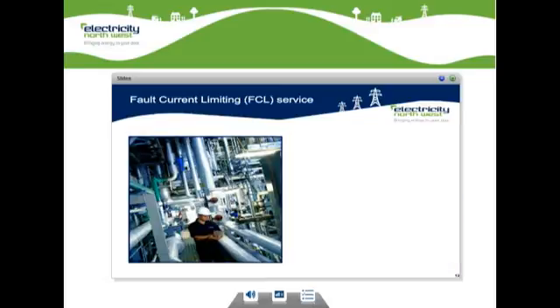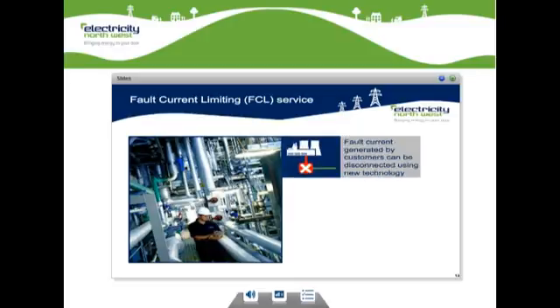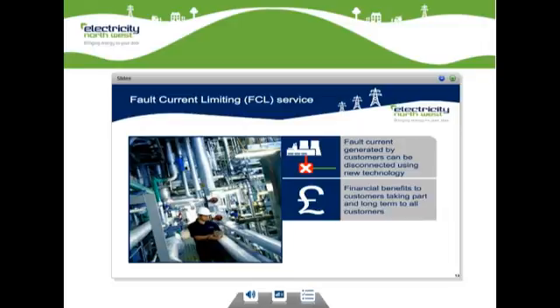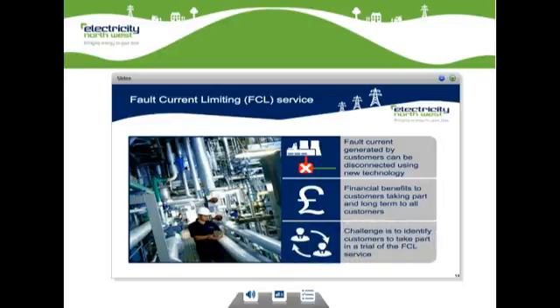The fault current limiting service enables us to disconnect the fault current generated by industrial, commercial and generation customers using new technology which will be trialled under Respond. This commercial solution will enable customers to earn rewards and will benefit all distribution customers through reduced reinforcement costs. We believe there is a significant amount of equipment out there connected to our network that is contributing to fault current that could be part of the solution. Our challenge as part of the project is to identify those customers who have such equipment, who are willing to be engaged with for us to explain Respond, and to see if they are willing and able to contribute to the project. We foresee a fault current limiting service could work like this.